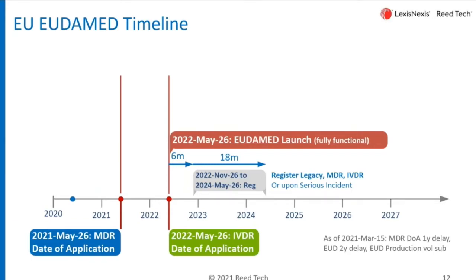Now a couple of timeline points we need to talk about. In the bottom left we see the date of application — delayed one year, currently at May 2021, just a few weeks away. The date of application for the IVDR is a year later, in May 2022. The current plan is for EUDAMED to be fully functional and launched on May 26, 2022. Since that launch date is after the date of application, the legislation builds in a six-month delay that starts all the effective items, regulations, and specifications related to EUDAMED reporting. One of those is the registration of medical devices, and there's an 18-month window for registration that goes out to May 2024 — you obviously want to be aware of that.